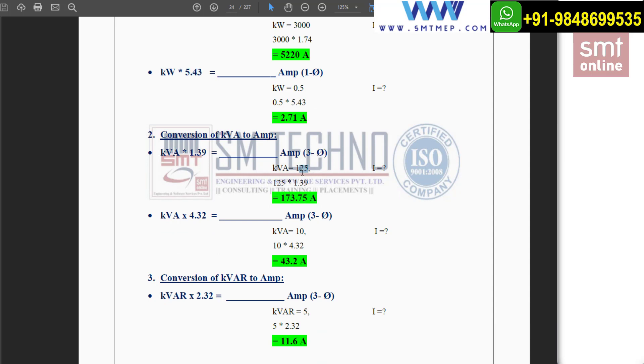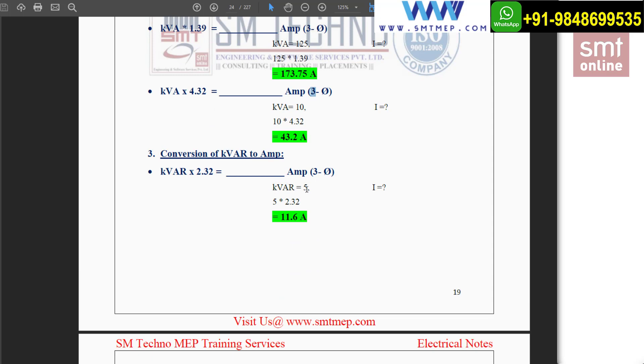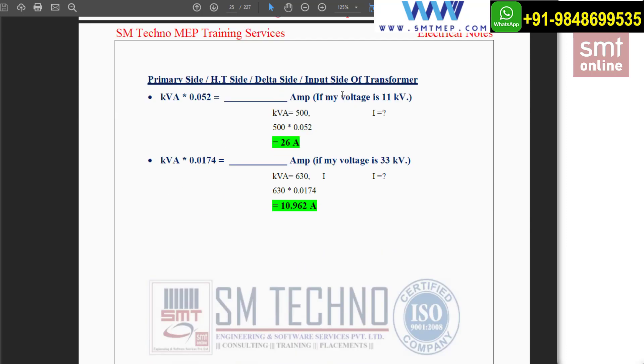For KVA: if it is 125 KVA, which is more than 25 KVA, it is a three-phase system — multiply 125 by 1.39 to get the current value. For 10 KVA, which is less than 25 KVA, it is a single-phase system — multiply by 4.32 to get 43.2 amperes. Note: there was a typing mistake in the slide marking 10 KVA as three-phase; it is actually single-phase. For 5 kVAR, multiply by 2.32 to get the current. For the high tension side, if the supply is 11 KV and transformer size is 500 KVA, multiply with 0.052. For 33 KV supply and 630 KVA transformer, multiply with 0.0174 to get the current.